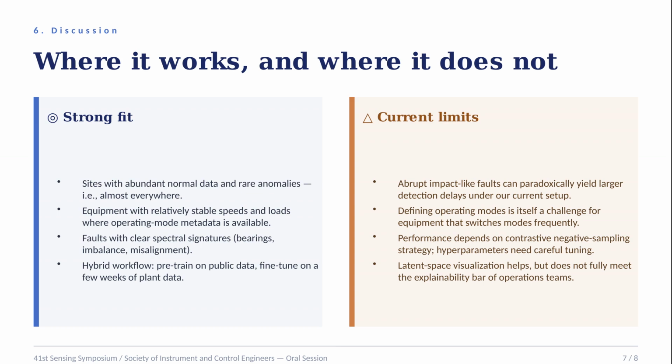That said, the method is not a perfect fit for every case. It works best where there is plenty of normal data, relatively stable operating conditions, and faults with clear spectral signatures such as bearing issues or misalignment. A practical workflow is to pre-train on public data and then fine-tune on a few weeks of site-specific data.